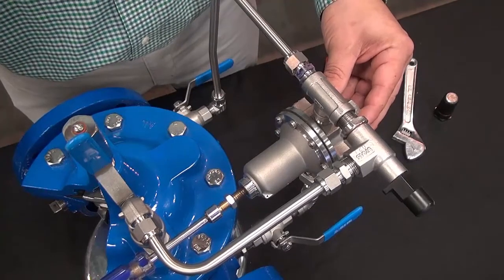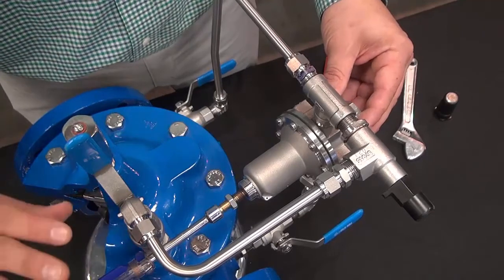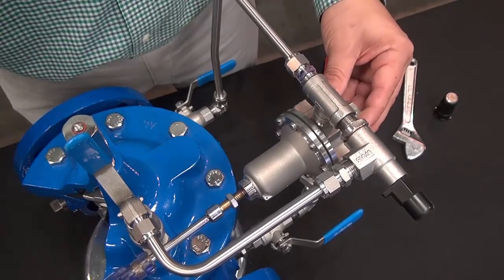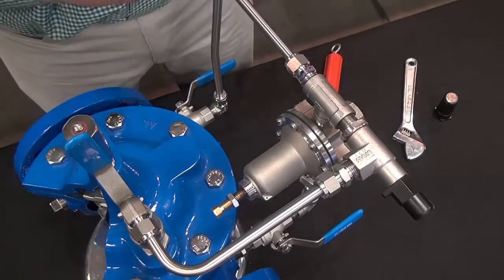Now half turn, wait for the change in the system, watch your gauges and slowly walk up the PSI setting on the CRD until you get to your desired setting.